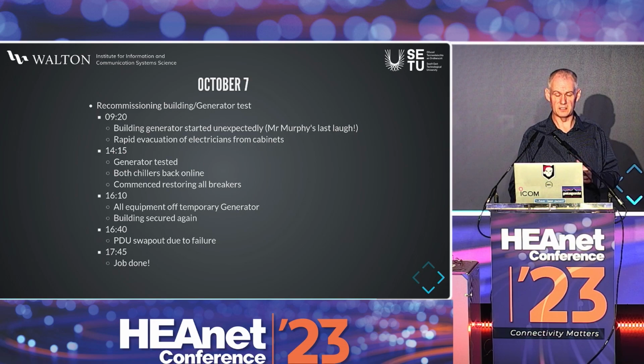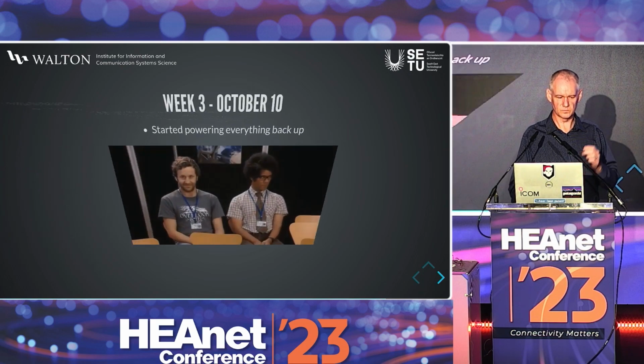We got back online, but a PDU failed, which caused a bit of an issue, and we've had a lot of those fail. Again, none of this stuff has ever really been switched off, even during Hurricane Ophelia, or ex-Hurricane Ophelia, we didn't switch off. So none of this equipment has really been switched off in quite a number of years.